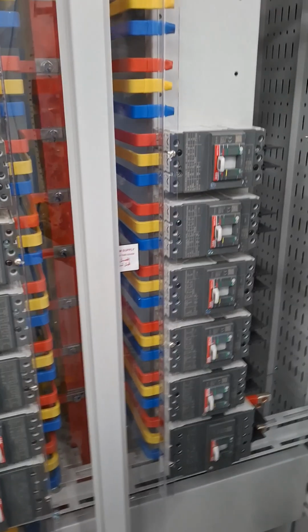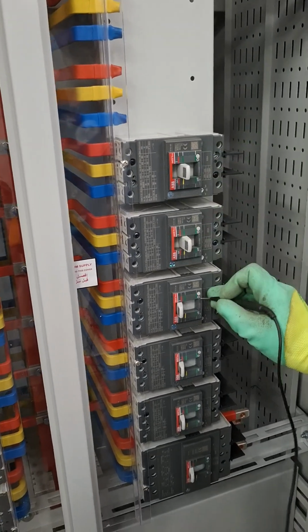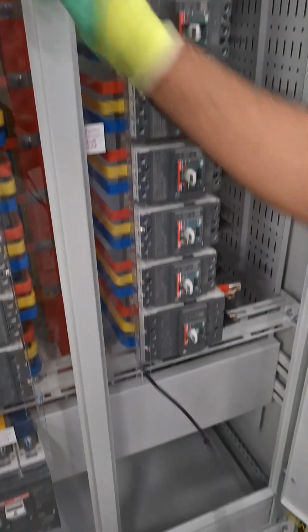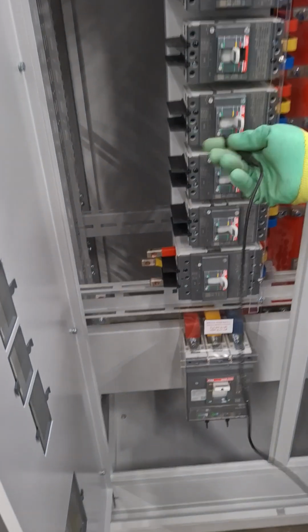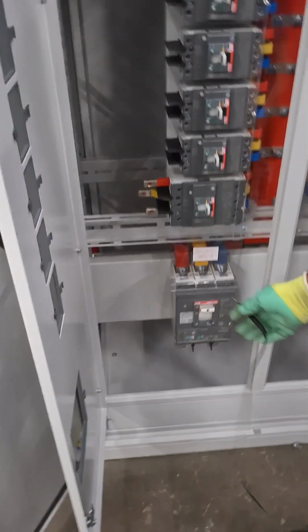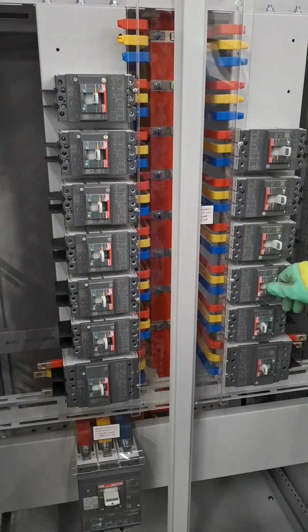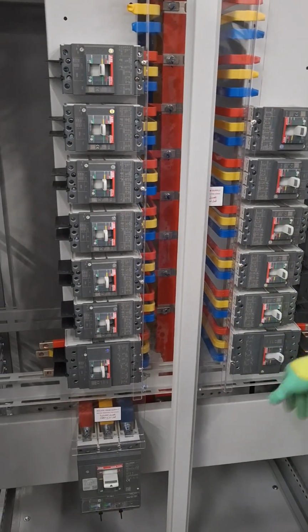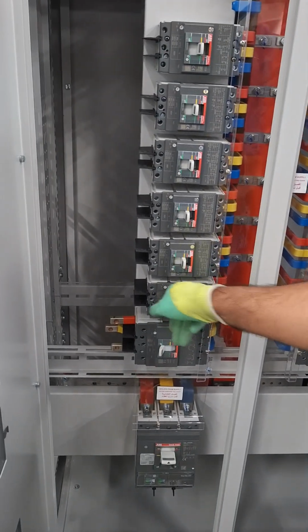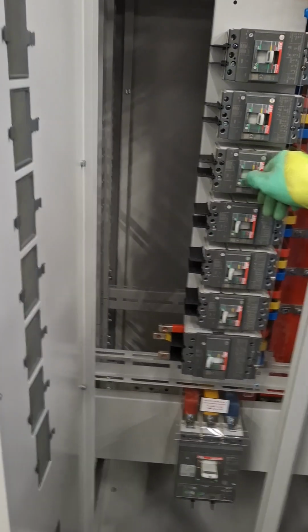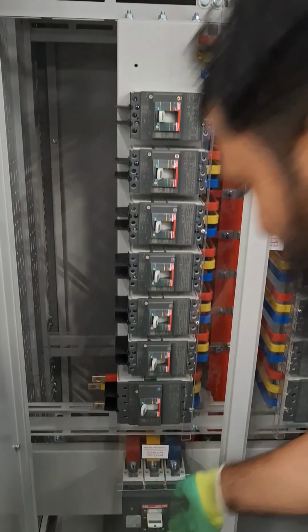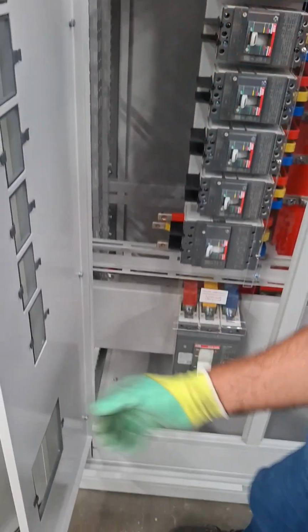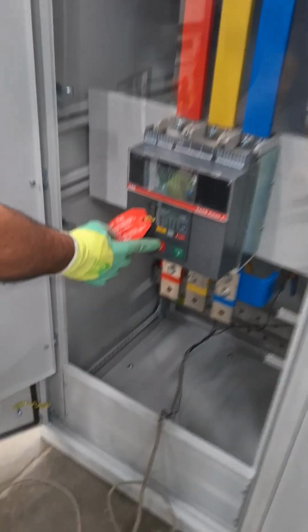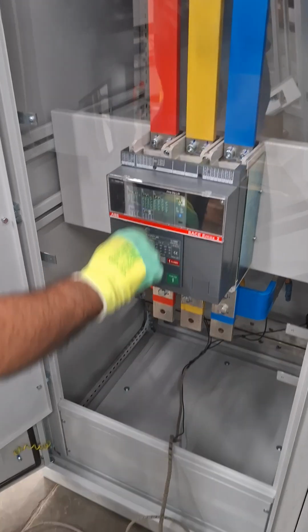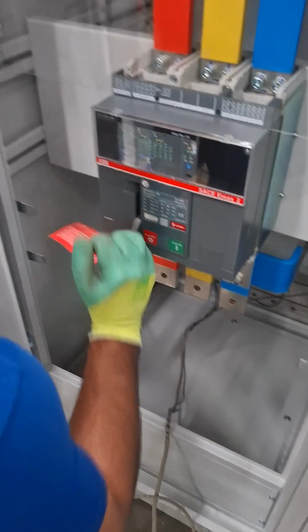Okay. Now we perform mechanical operation with the breakers one by one. Okay. Because sometimes when we apply high voltage, the breaker gets stuck at the on position. Okay. Overall breaker okay. On, off, and trip position also. Now we charge the breaker manually.